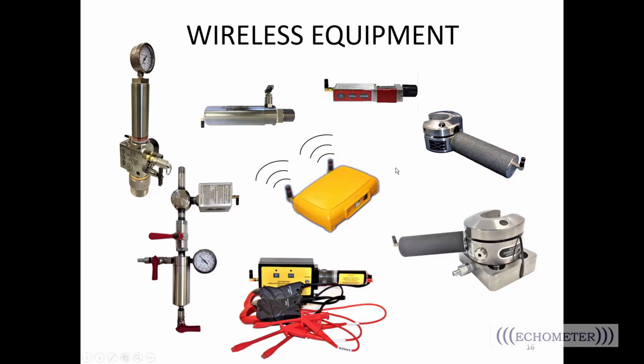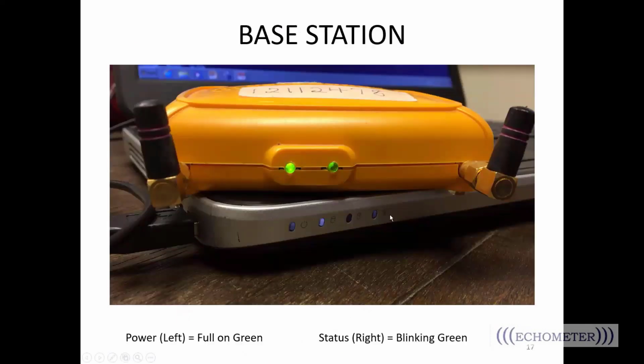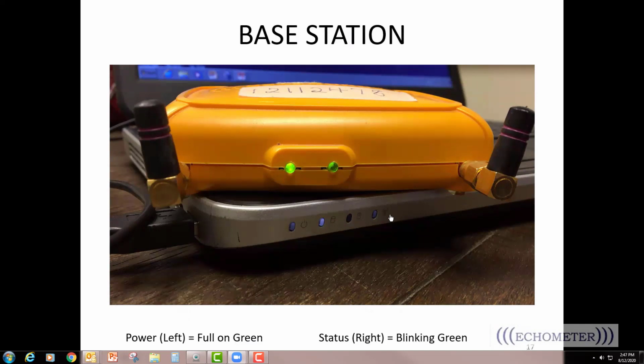So with the wireless equipment, it's all about communication, right? We're talking about the communication, the signal strength, the sensors, and so everything sort of revolves around the base station. So one thing that we want to make sure and make clear, the base station basically represents your well analyzer and all of your cables. And so even though it's this little yellow block in plastic, we really want to stress that this is probably one of the more expensive sensors that you have, right? So this is what holds the license. This is what holds the key to all of the communication. This is what connects to your laptop.